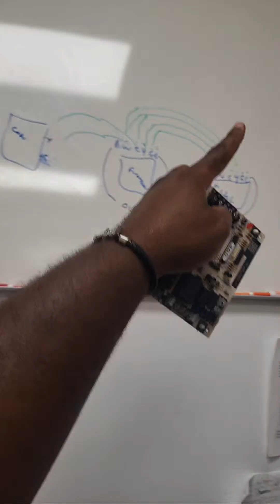This is low voltage troubleshooting 101. Next, remember I already had the indoor wires hooked up and the unit ran, so I turned the power off. I disconnected my low volt wires outside and connected my low volt wires inside, doing the same thing again. I disconnected everything first, all the wires inside and out, the unit stayed on. Then I turned it off, connected my indoor thermostat wires, kept the outdoor wires off, turned the power on, and the unit came on. Cool.